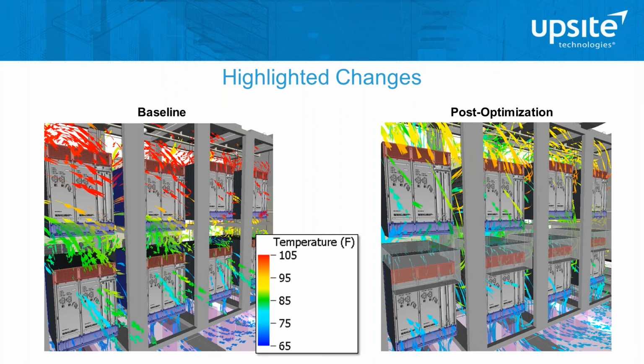The problem was he had no control internal to the cabinets. The cabinets were obviously laid out internally by the IT department. But the IT department was demanding that the alarms be switched off. And the facility managers had to do this, literally, by lowering the temperature of the room. In other words, they had to lower the supply temperature to 11 degrees centigrade. That meant enormous losses in energy efficiency. So you're absolutely right. The room temperature does not necessarily have a direct link to the inlet temperatures of the individual pieces of kit, which is really where the alarms start to sound off. And that again goes to the complexity of the airflow.